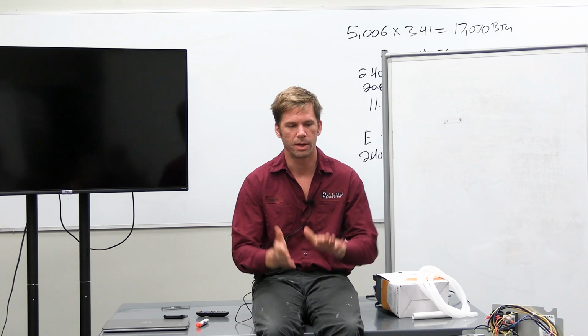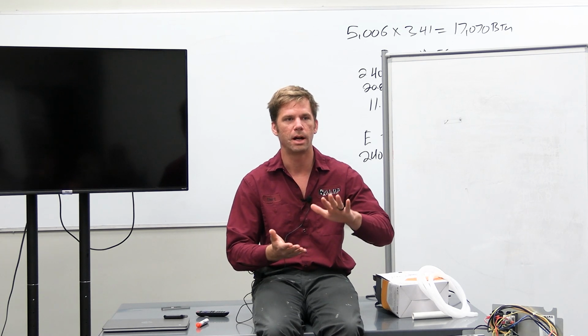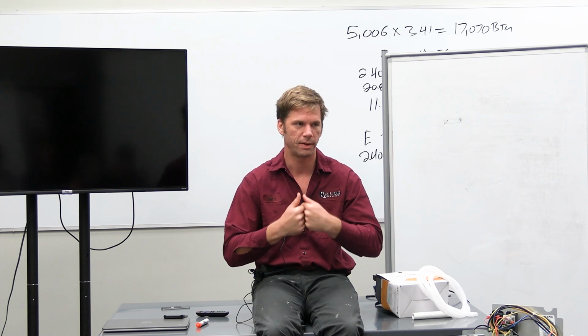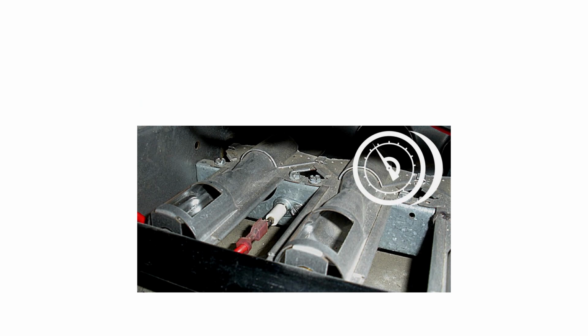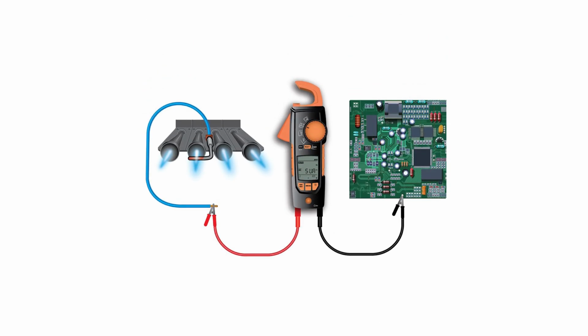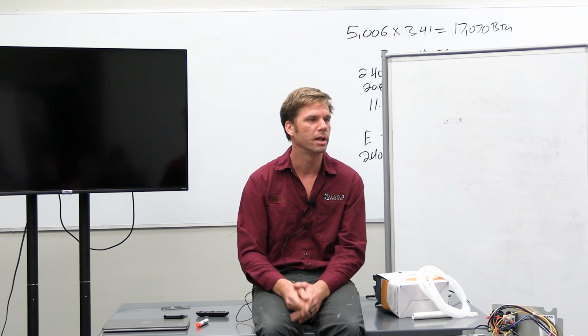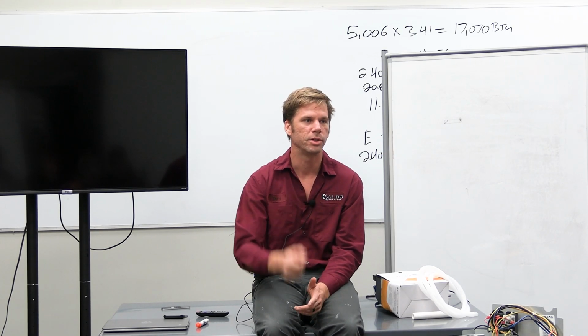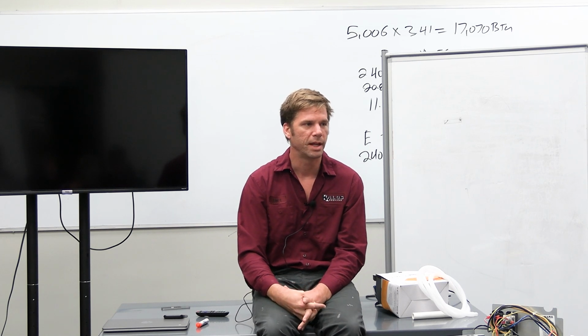It gives it just an amount of time to get really red hot, and then it opens the gas valve. And the next safety is the flame sensor. So you have a rod that sticks straight into your flame, and it's nothing but just a metal rod with a wire coming back to the board. Nothing fancy. It needs to be actually in a location where the flame can hit it. So if it's been knocked or moved, you got a problem. You can usually grab that and adjust it, put it right back in the flame.